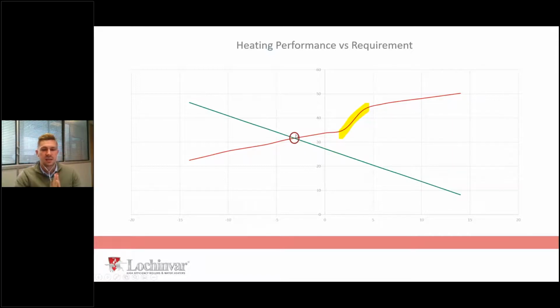And just before we go on to the next slide, should have done a poll question for this one, but we didn't. The kilowatt rating of the electric air source heat pump drops quite drastically when we get to an outside air temperature of 4 degrees centigrade. And then it levels back out when we get to an outside air temperature of 2 degrees centigrade. So it's an interesting one, but basically that's the point in time where the refrigerant inside the air source heat pump, whether it be R410A or 407C, whatever heat pump you're using, it will probably be the first time that refrigerant's gone below freezing. It's the first time it's below 0 degrees centigrade. So the refrigerant's freezing, we're pulling a load of air across that evaporator, loads and loads of air. So if we're pulling a load of air across an evaporator which is freezing, what happens is any humidity in the air stays behind. So that turns to ice.